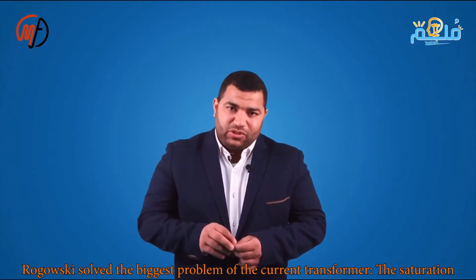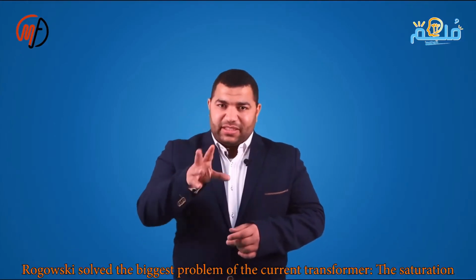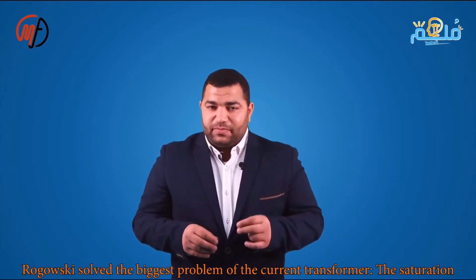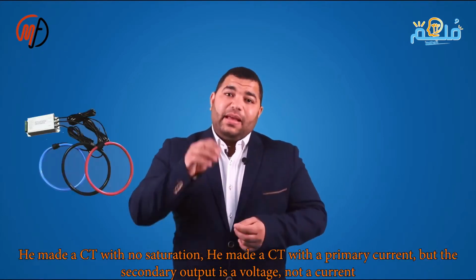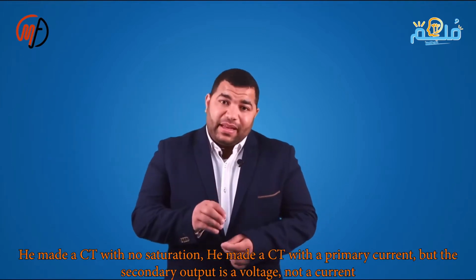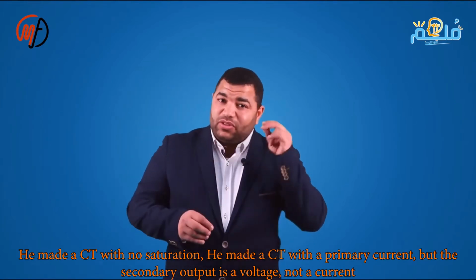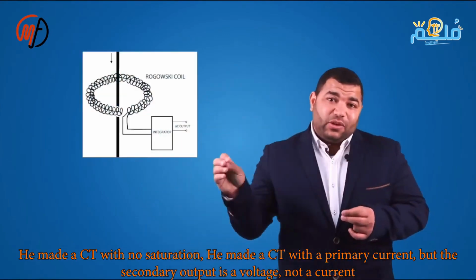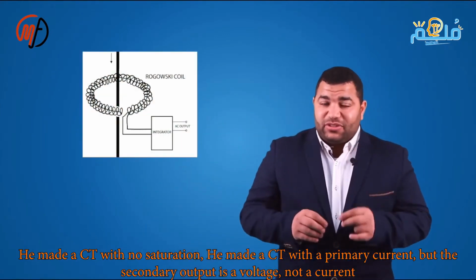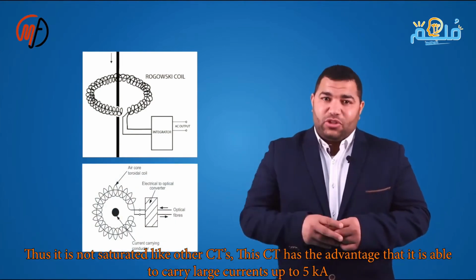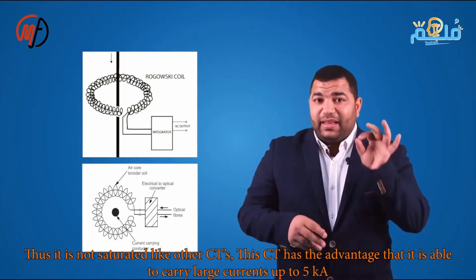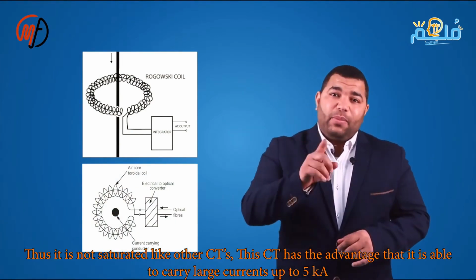The scientist Rogowski solved one of the biggest problems with CTs, which is the saturation issue. He invented a CT that doesn't experience saturation at all. He designed a CT that has an input current on the primary side, but on the secondary side it has an output voltage instead of current. This means it doesn't saturate like other CTs, and it can handle high currents up to 5 kiloamperes.